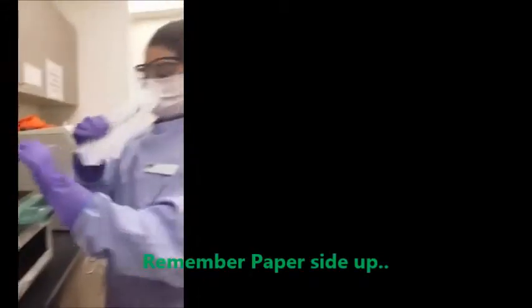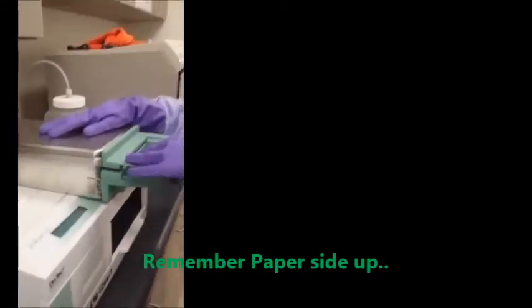Any loose instruments that you might have will go in the Statim. Place the loose instruments in the sterilization packs and place the packs paper side up into the cassette. Close the cassette by putting the lid on top. Place the cassette back into the Statim. You will hear a slight click upon putting the cassette inside the Statim.